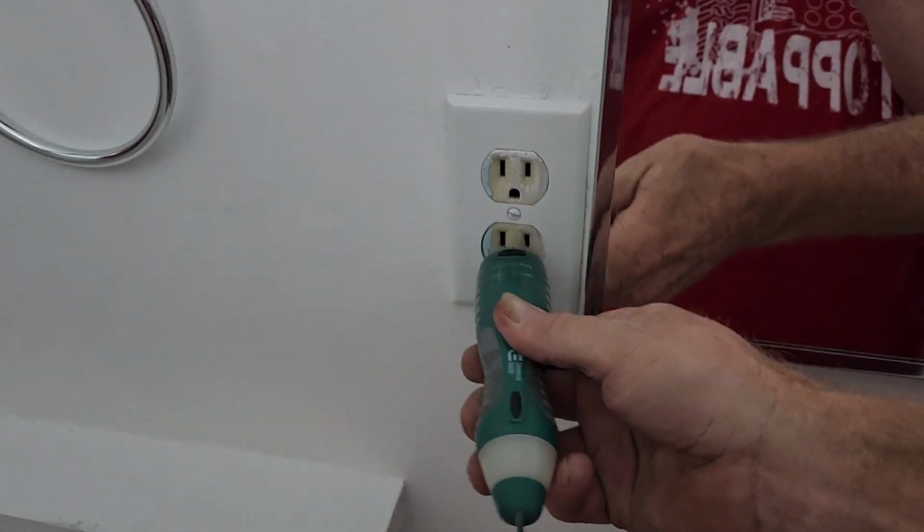no ground fault protection on the outlet. And then there are gaps or cracks in the shower pan. So you have one outlet, this outlet right here. Just recommended to add ground fault protection. I think it actually turns green. Yeah, it's wired correctly. It has ground, but it doesn't have ground fault protection. It's grounded, but it doesn't have GFI protection. Now those cracks in there, that's actually tile.